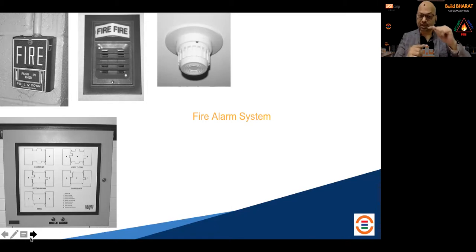When making shop drawings, it must be separately indicated what height the fire alarm panel should be, what height the manual call point should be placed at. You may have tolerance - you can't get exactly 1.2 meter height in every floor and every place. But if you've given a tolerance of plus minus 200mm, at least the integrator can follow that tolerance to install the manual call point, strobes, repeater panels, fire alarm panels, and so on. I've seen during my audits various places where the fire alarm panel is placed in an area where it's supposed to be hidden.